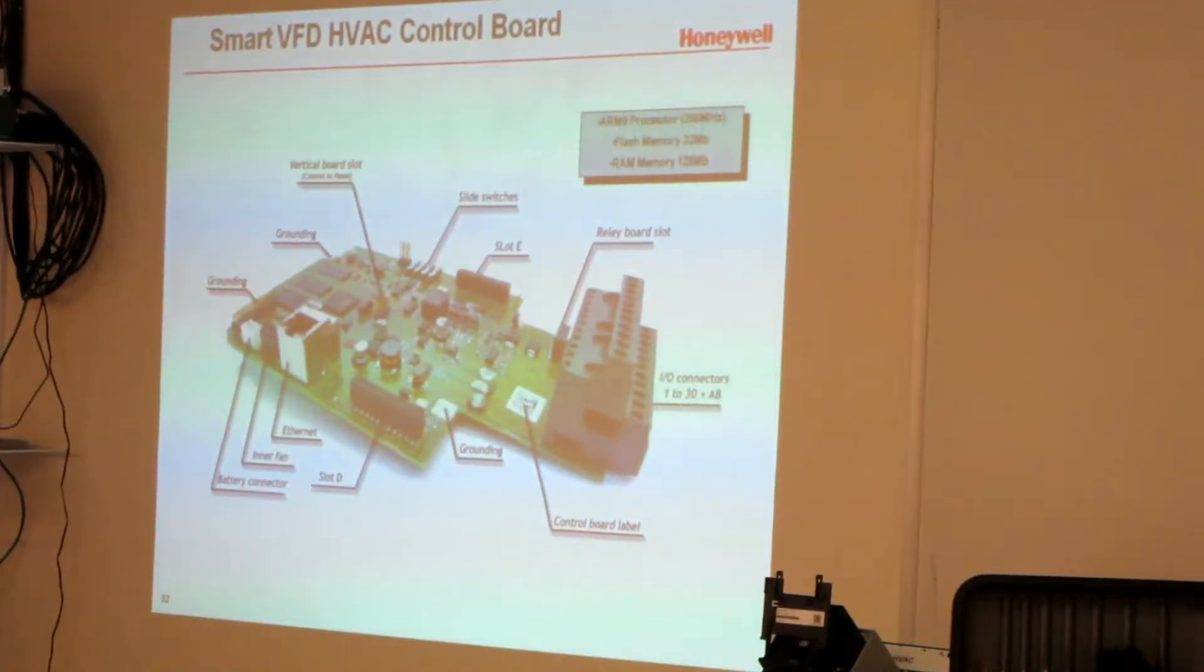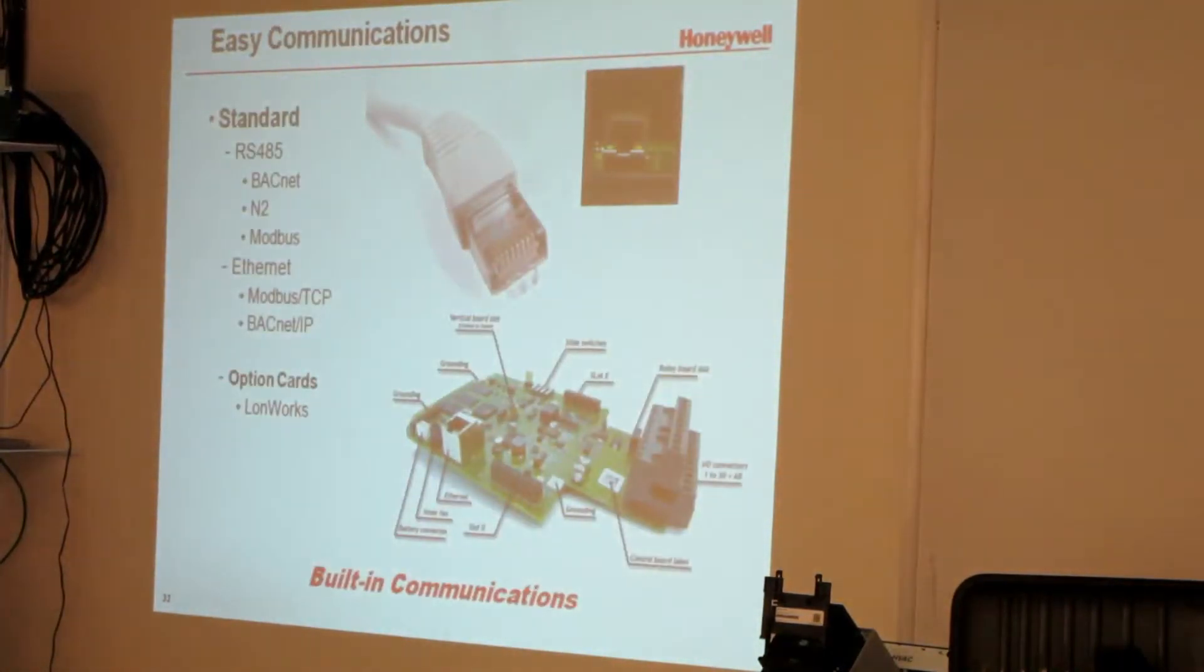I've had one job where the guy needed more than the I/O that came with it. And he's one of those engineers, the control guys who likes to have anything he's got uses every single function that thing has. And so he got NXS drives and he had a bunch of boards on them. When one thing turned on, it turned on another thing, it turned on another thing and so on. And you have that capability built into this thing to do that. I'll get into that in a little while. So the slot is here, it just plugs into the side, and the connectors here. The connectors are all numbered and they correspond to the wiring diagram. And we'll get into those in a minute.